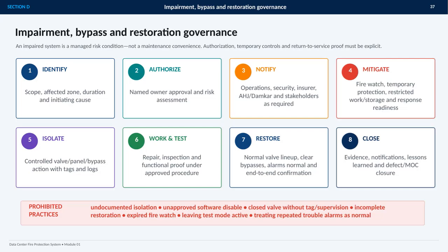This section treats an impaired fire protection system as a managed risk condition, not a maintenance convenience. The process begins by identifying the affected zone, duration, scope, and initiating cause. Then a named owner authorizes the impairment, supported by a documented risk assessment. Required stakeholders are notified, including operations, security, the insurer, the AHJ or Damkar, and others as applicable. Mitigation must be active, with measures such as a fire watch, temporary protection, restricted work or storage, and confirmed response readiness.